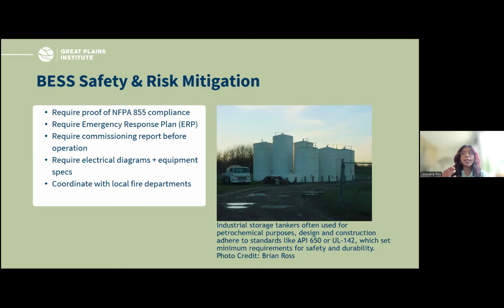A very important addition to the latest version of NFPA 855 is the requirement for strong coordination with local fire departments. Usually the fire departments are volunteer fire departments, so NFPA 855 requires annual training of the volunteer fire department, so that if there are any changes, the county will be notified, and the folks who will be first responders in case of an emergency will be trained every year in case any risk does take place.